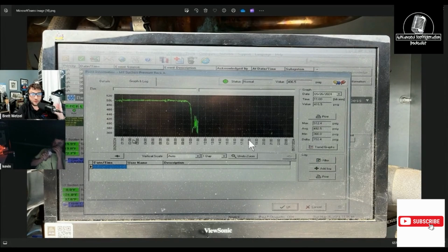As soon as one of the low temp circuits would stop feeding, the discharge temperature went down in the toilet, and then basically didn't allow it to warm up the suction line as much as it was. Because you can see, like, it was feeding here, but it wasn't doing really much. Like, it just kept wanting to feed. And this is when he started beating it. Right around this zone. So then it started feeding fine.